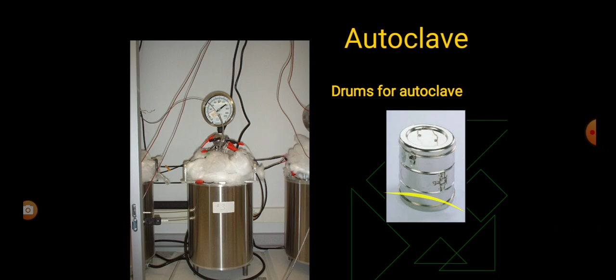See, this is the jacketed autoclave, with exhaust valve and safety valve. The whole principle of the autoclave is water boiling, which releases steam. That steam comes into direct contact with the articles kept inside, on the cooler surfaces. So what happens? All the microbial proteins are coagulated during the holding temperature of 121 degrees Celsius, 15 lbs pressure, for 15 minutes. We should remember this autoclave holding temperature: 121 degrees Celsius, 15 lbs pressure, 15 minutes.